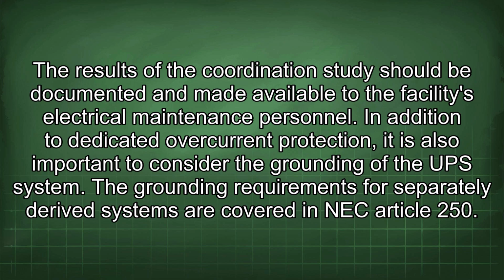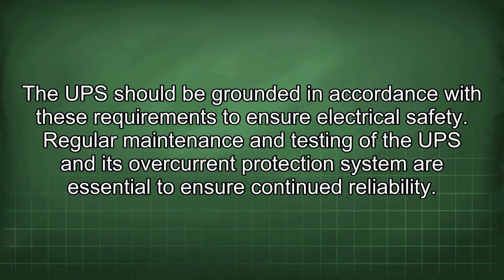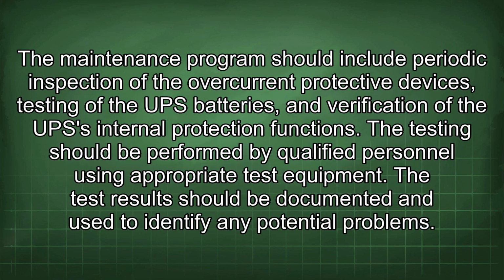In addition to dedicated overcurrent protection, it is also important to consider the grounding of the UPS system. The grounding requirements for separately derived systems are covered in NEC Article 250. The UPS should be grounded in accordance with these requirements to ensure electrical safety. Regular maintenance and testing of the UPS and its overcurrent protection system are essential to ensure continued reliability. The maintenance program should include periodic inspection of the overcurrent protective devices, testing of the UPS batteries, and verification of the UPS internal protection functions.